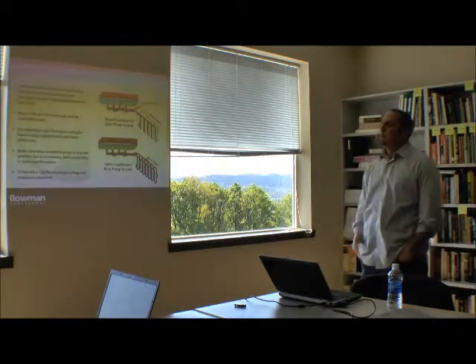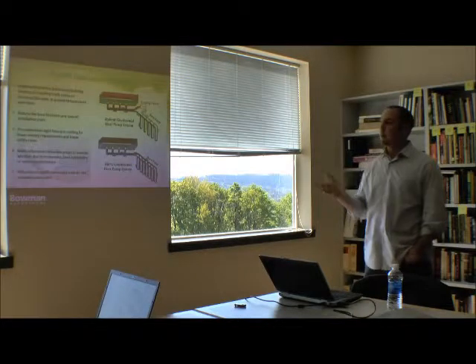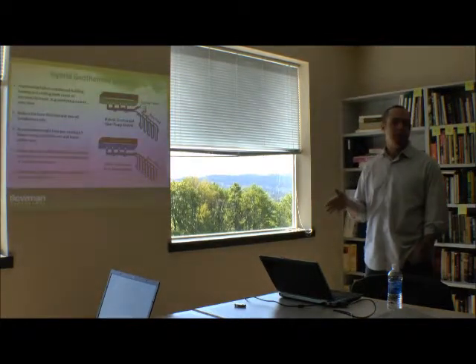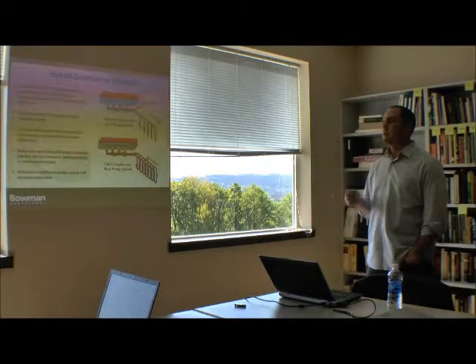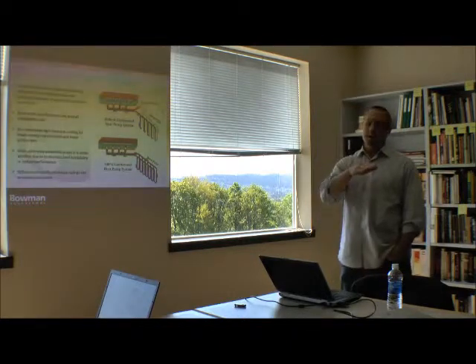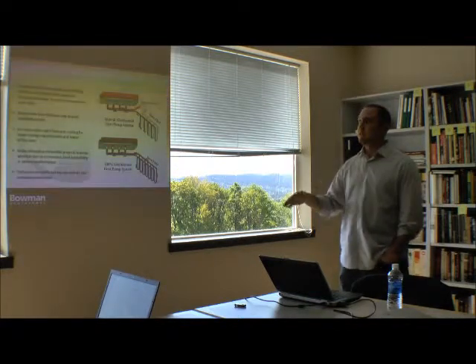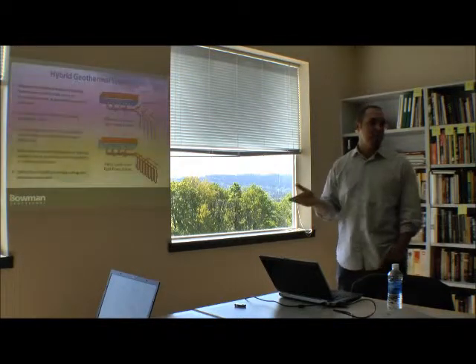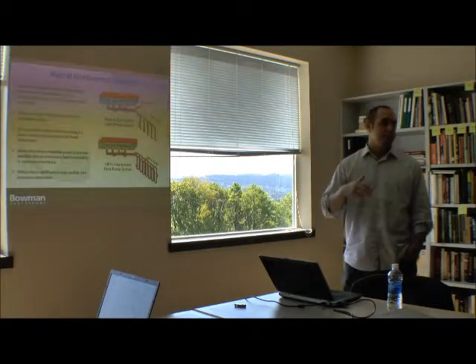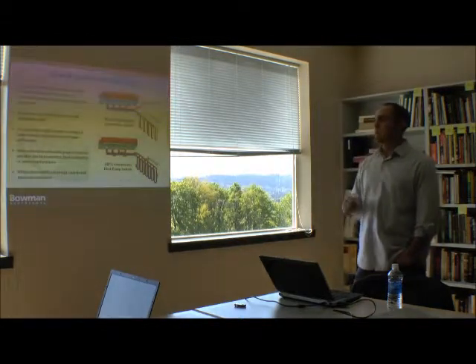Hybrid systems are optimal when you have balanced heating and cooling loads. This is why they're very popular back east where they have distinct seasons. When buildings are cooling dominant or heating dominant, you're either continuously dumping heat into the ground or pulling it out, which over time raises or lowers the ground temperature by 10 to 15 degrees over 20 years — or even over 5 to 10 years. That changes system efficiencies and nullifies the reason you installed the system in the first place — to save energy and reduce operating costs.